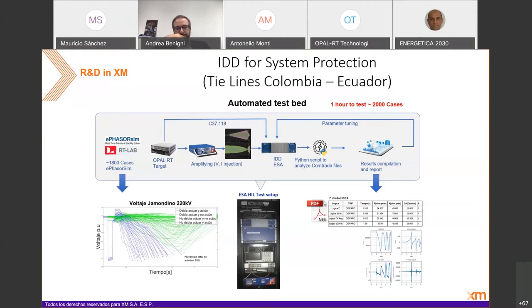So we implemented a special protection scheme using synchrophasor technology and also customized protections like a kind of stability detection, the stability assessment of the interconnection in the south of Colombia that can trip in very fast times, in milliseconds.